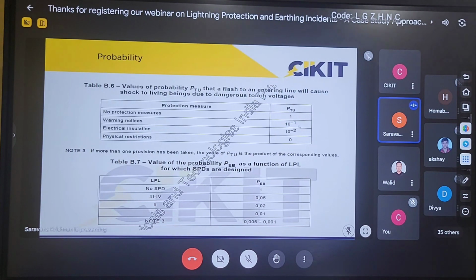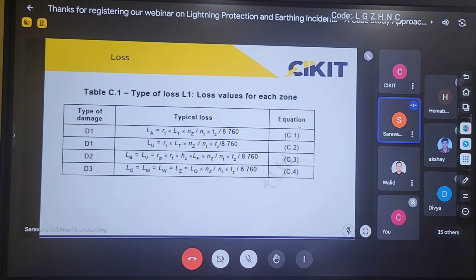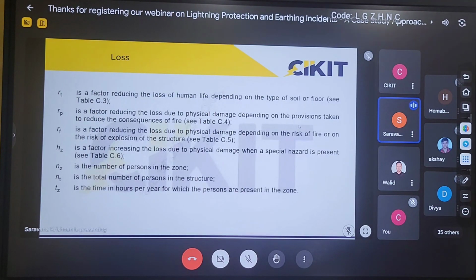So this is the formula for calculating the corresponding loss. Here, if you observe, the different parameters involved are RT, LT, NZ, NT. I will explain the parameters in the next slide. The first one is RT, the factor related to the type of soil and floor. If lightning current is discharging and the surface layer has higher resistivity, then the effect of step and touch voltage will be reduced. In this parameter, we consider the type of soil, that is the resistivity of the soil, and the type of flooring we have. If it is a normal concrete floor, the effect will be lower. But if I have any insulation over the concrete floor, the effect can be further reduced.